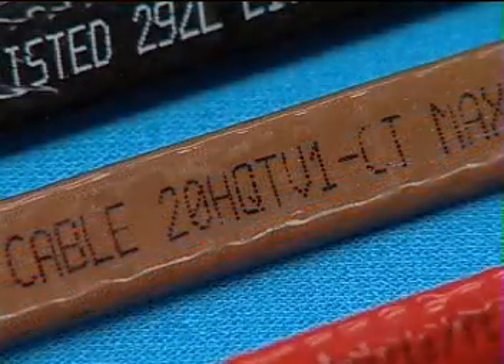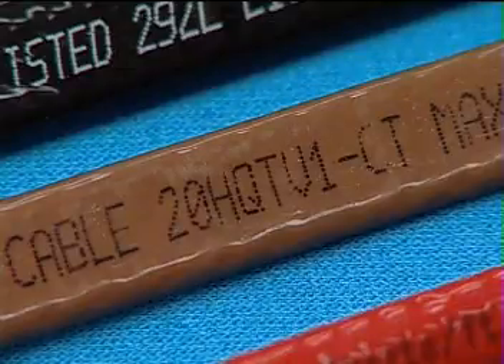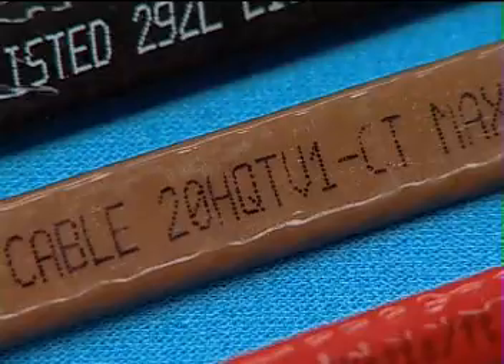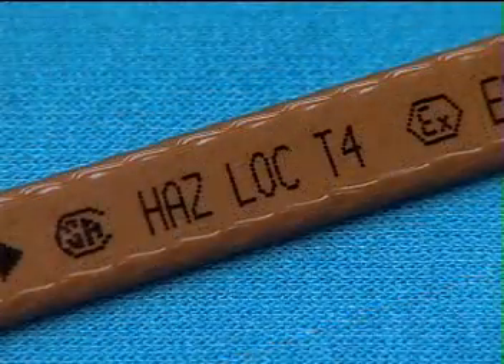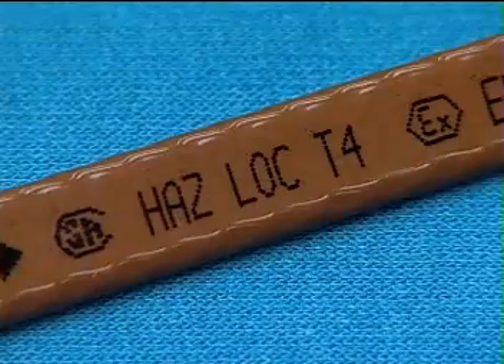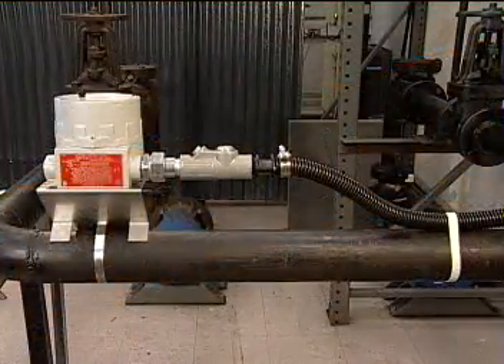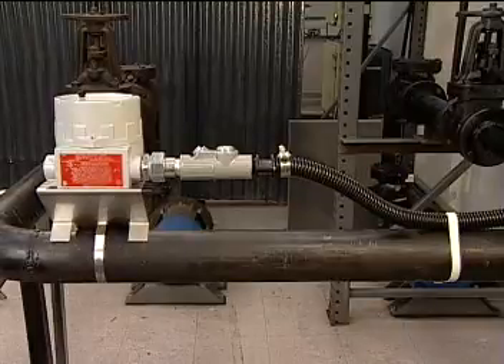Verify that the heating cable is designated for the area by looking at the printing on the outer jacket. It should have an H as the first letter in the product family catalog number. Also make sure the cable T rating is suitable for classification of the area. This demonstration will install an HAK C100 power connection.